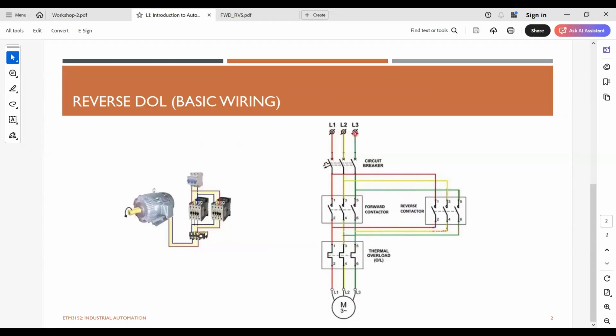So we have the three-phase line in, which goes to the main circuit breaker. So main circuit breaker is used for disconnecting the downstream devices. Sometimes it also offers overcurrent protection. Then it comes to the forward contactor, this one. So if you want to run the forward direction, what you can do is turn on the forward contactor. So that will allow the current to flow to the motor and it will rotate in one direction.